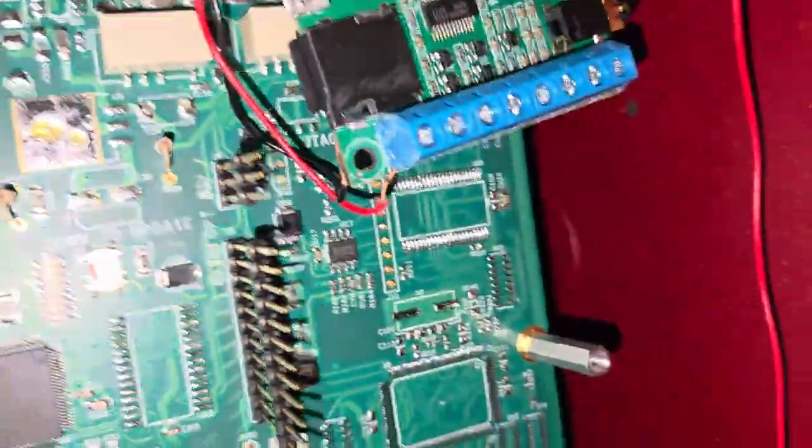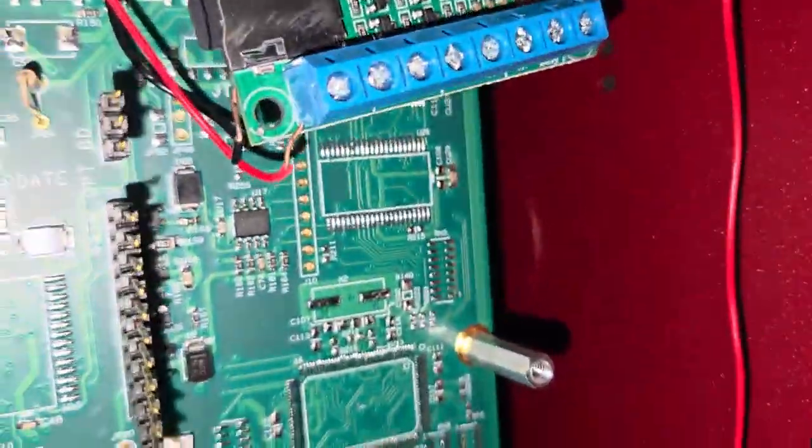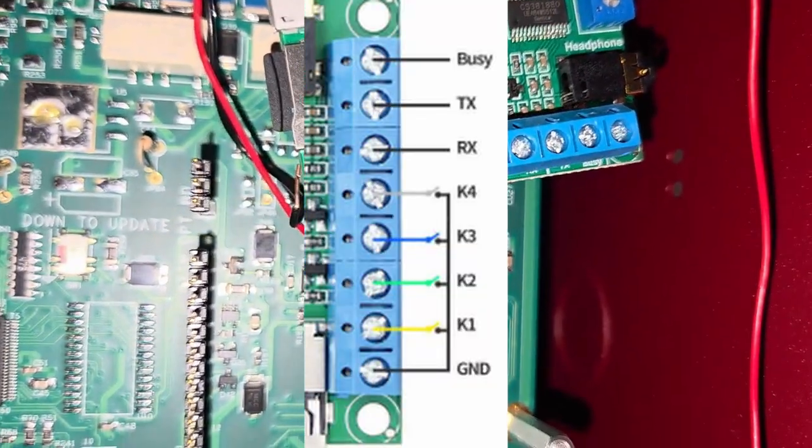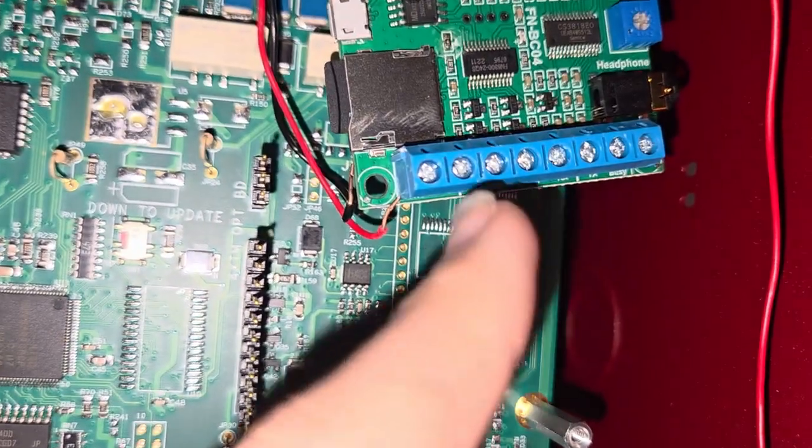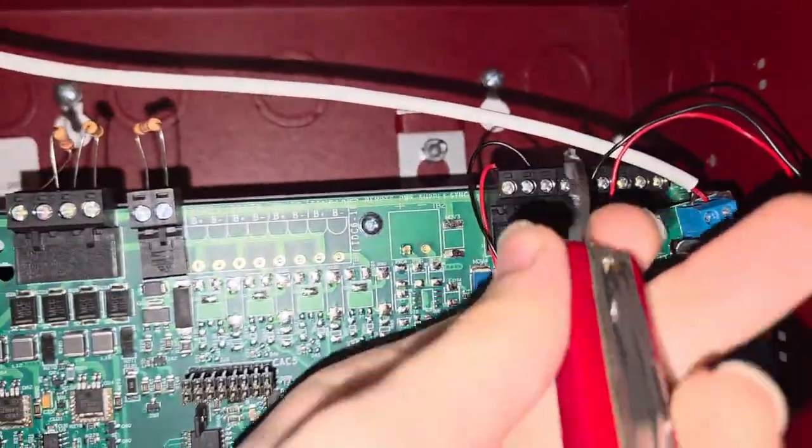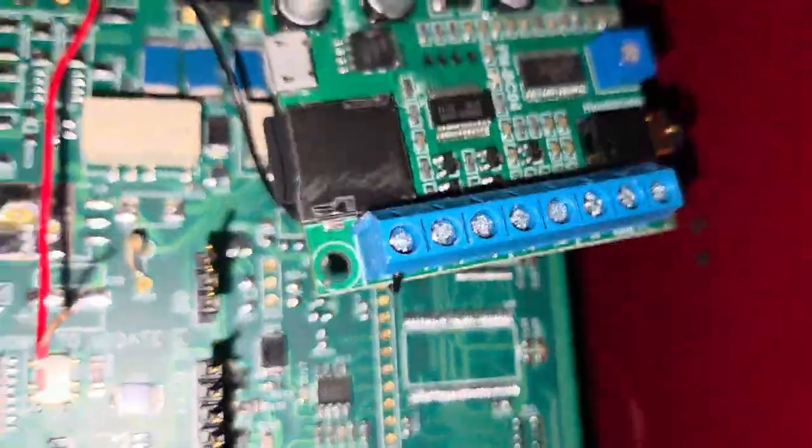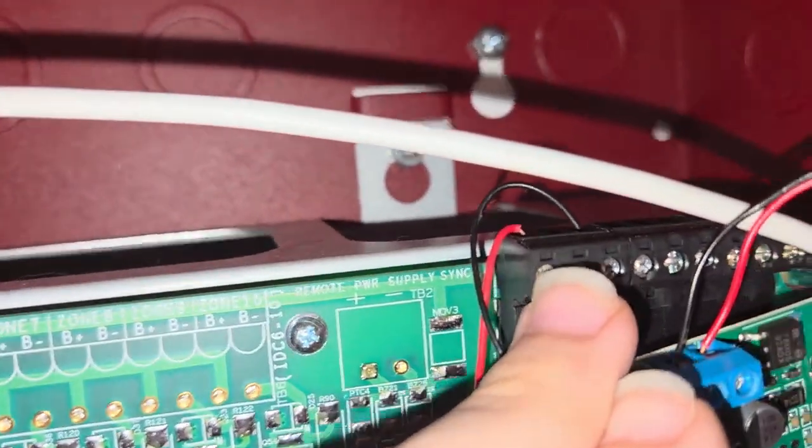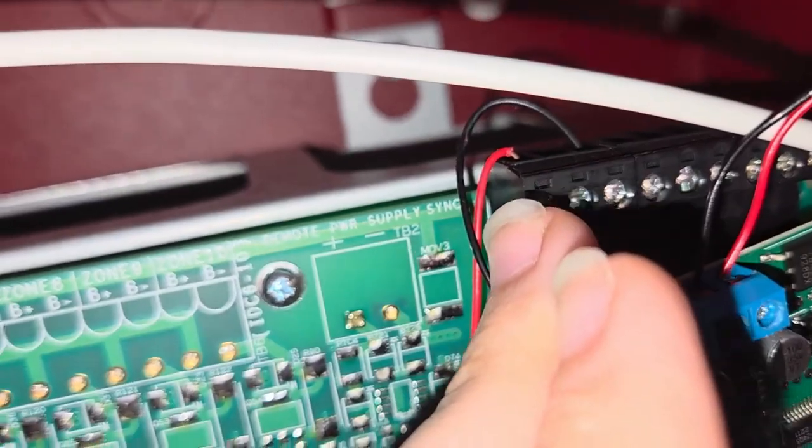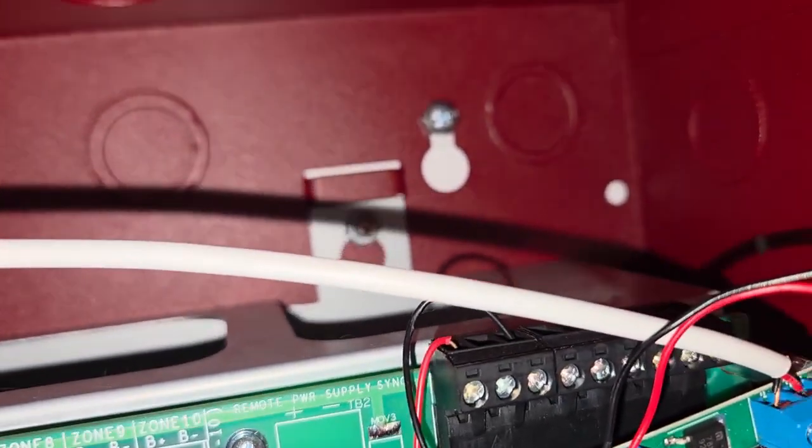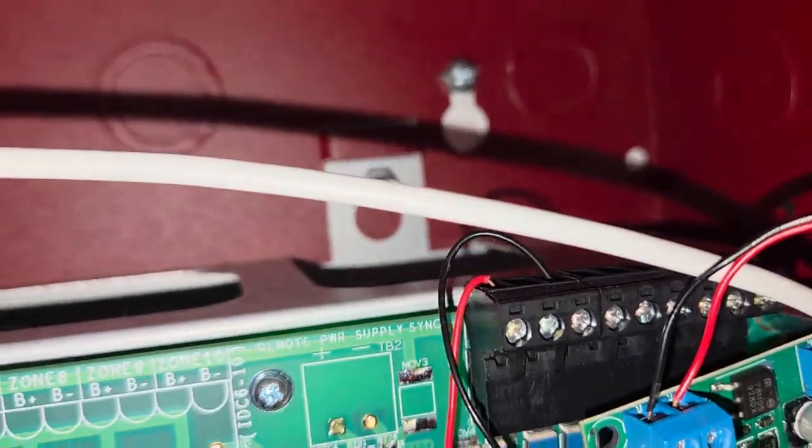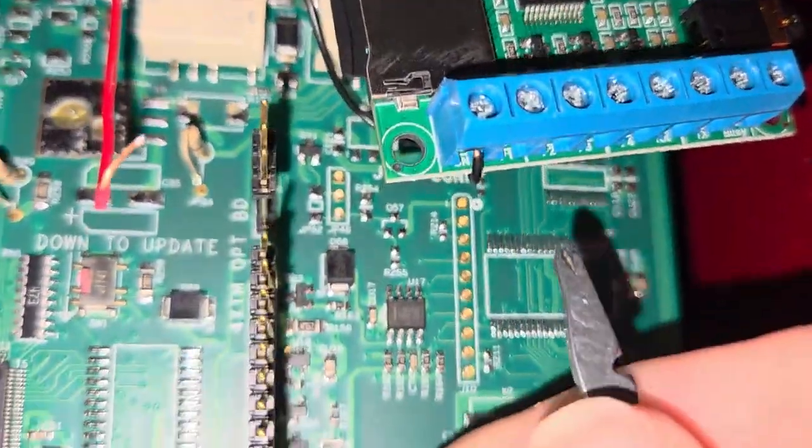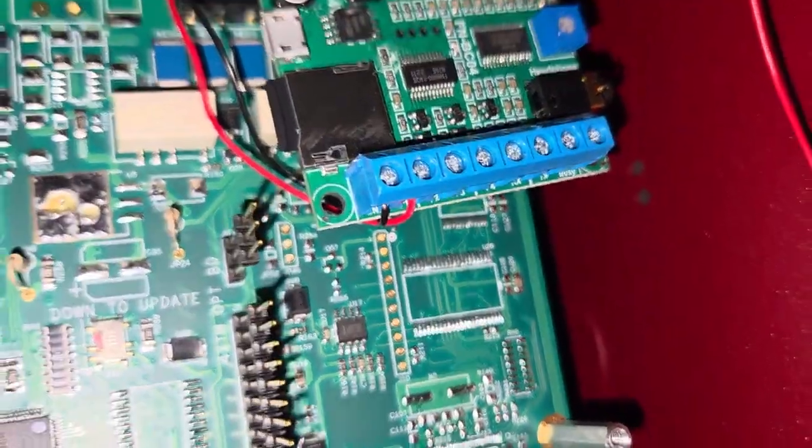And then here's where it's slightly more complicated. These are your relays. I'll pull a diagram up right now of what they are. But really the only thing you need are the two relays on the left. You're going to want to hook up your common to the common right here. Like that. Then you're going to want to take your normally open relay on your panel. This is important: take your normally open relay on your panel. If you don't know what that is, or where that is on your panel, just look it up on the internet, or if you have your manual, it'll be in there as well. Take your normally open relay and then put it in the slot right next to the common.